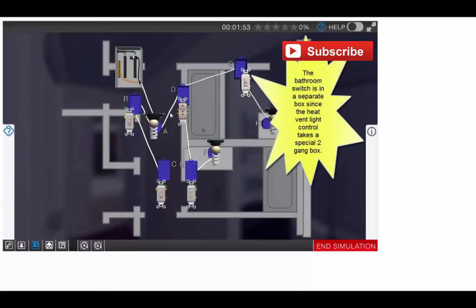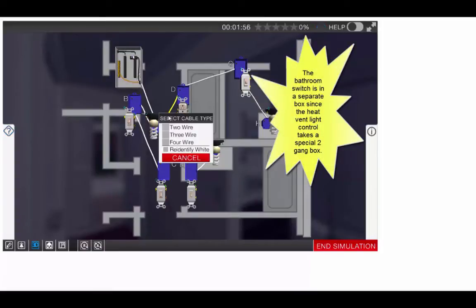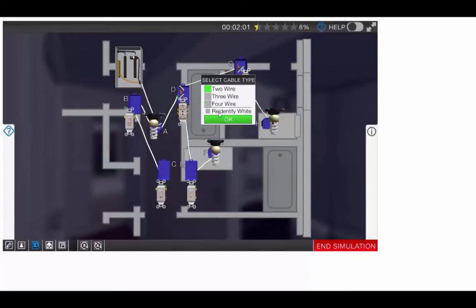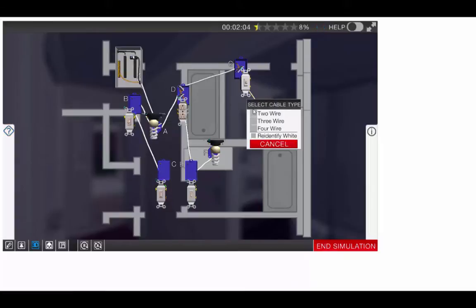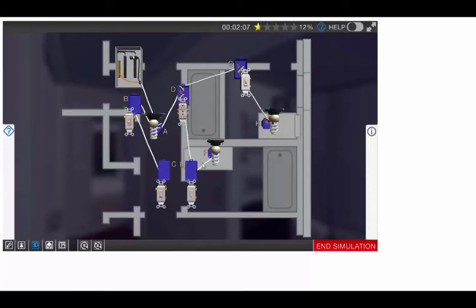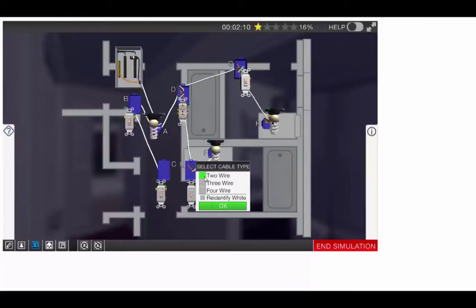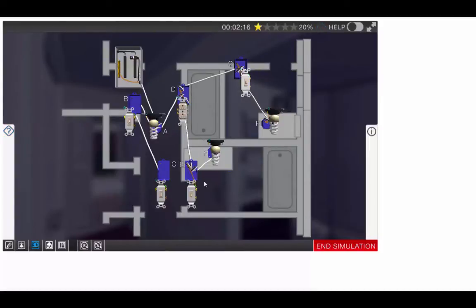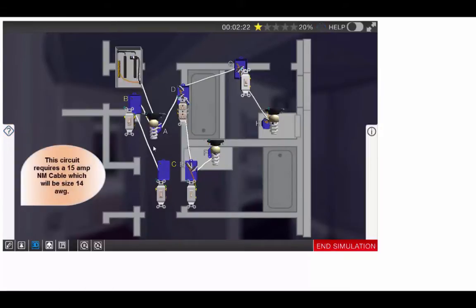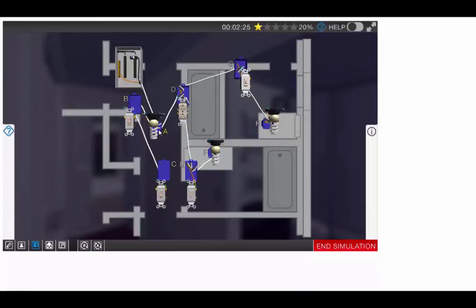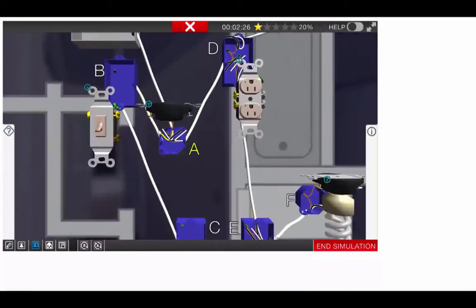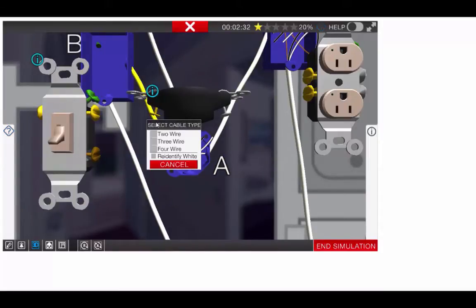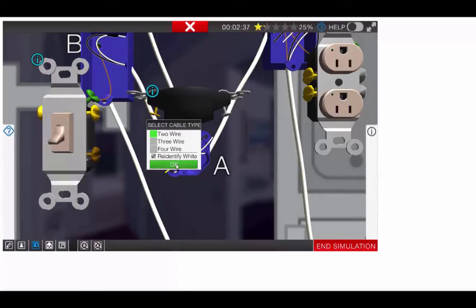So coming to box D, which is our receptacle, we'll need a 2-wire Romex. We'll also need a 2-wire Romex going to the master bath to the light fixture. In the hall bath, we'll need a 2-wire going to the light fixture and a 2-wire going to the switch also. Now coming in to the hallway, we have two 3-way switches. In this case, our main power is coming in to the light fixture, so we'll need to wire to the first switch with a 2-wire Romex, but we're going to have to use the white as a hot. So we're going to re-identify the hot.